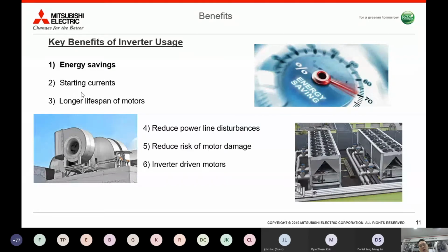Next will be starting current. When you use the inverter to run the motor, there will be no high starting current as compared to the conventional methods of using starters such as direct online, Star Delta, or Autotransformer. All these starting currents will be eliminated. It also has an impact on the motor itself, because the inverter starts the motor slowly and stops the motor slowly. This gives the motor a longer lifespan, and reduces power line disturbance and the risk of motor damage.